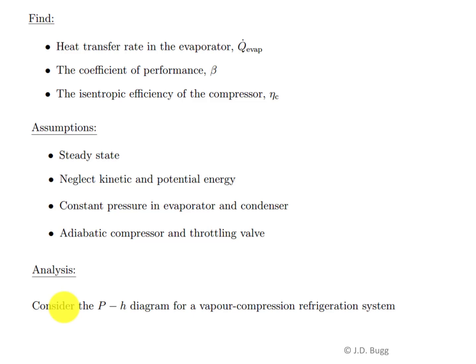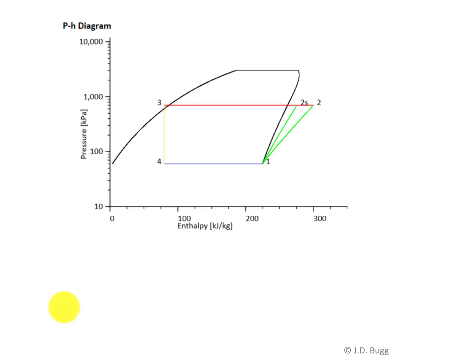We need to determine where those pressures and enthalpies that were measured correspond to on the diagram. The best way to do this is to recall what a P-h diagram looks like for a vapor compression refrigeration system. So here I'm showing just a typical P-h diagram. We have pressure on the vertical axis, enthalpy on the horizontal axis. This is the saturated liquid line, and this black line here is the saturated vapor line.